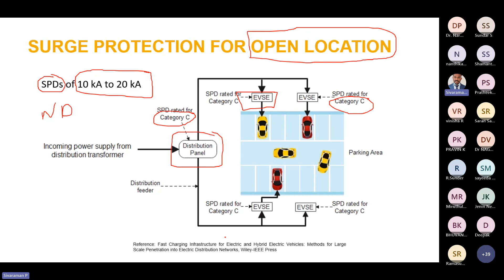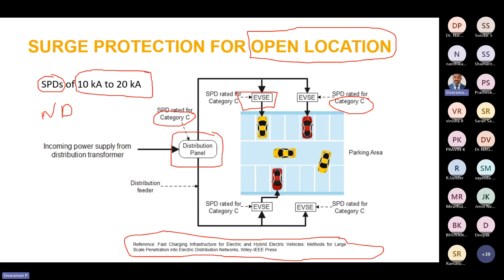The SPD has some specifications, the main one called nominal discharge, ND. The nominal discharge of the SPD shall be 10 kA to 20 kA. This reference has been taken from the book I told you about in the beginning of this session, and this is for the surge protection for the open location.